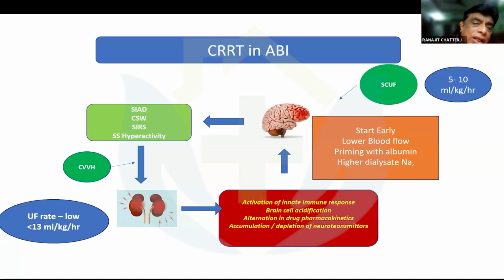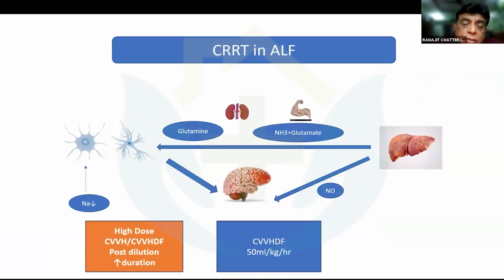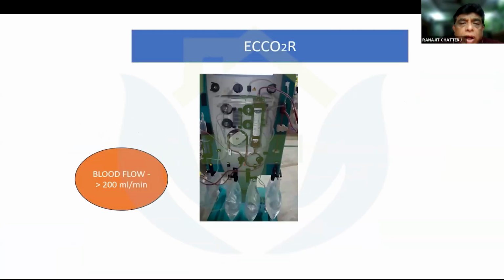Whereas if the same thing moves towards where the kidneys are injured, I start with an ultrafiltrate rate not at 20 to 25. At this present moment, I'm going for CVVH with severe hemodynamic instability. I might have to go for a lower ultrafiltration, because it has been seen that if the ultrafiltration crosses 30 ml per kg per hour, there is again hypotension. Now, in case of acute liver failure, if the patient is hemodynamically stable, I have to slowly increase my dose up to 50 ml per kg per hour to remove that ammonia. The ammonia will not be removed at a dose of 20 to 25 ml. So this is the variation of dose that we have in different forms of therapy.